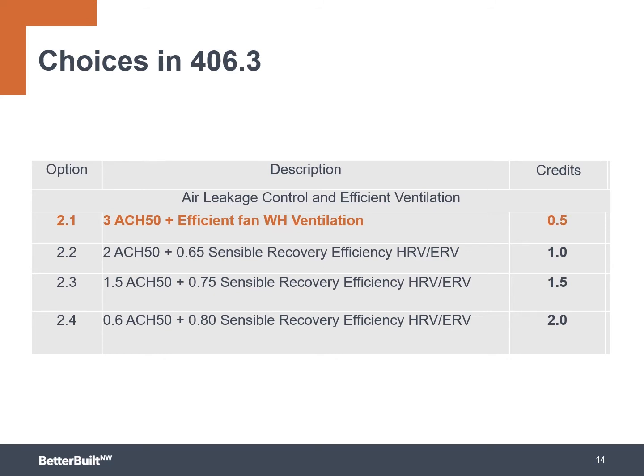The first credit we'll talk about is option 2.1. It's worth half a credit in single family, and it's by far the most common, popular, and cost-effective measure in this category. We're talking about getting the home to 3 air changes per hour from 5, which was the prescriptive requirement, and using an Energy Star rated fan or fans dedicated to whole house ventilation. This credit doesn't have a specific required way to get there, meaning you can use exhaust only, supply and exhaust, or a packaged balanced system such as a heat recovery ventilator.